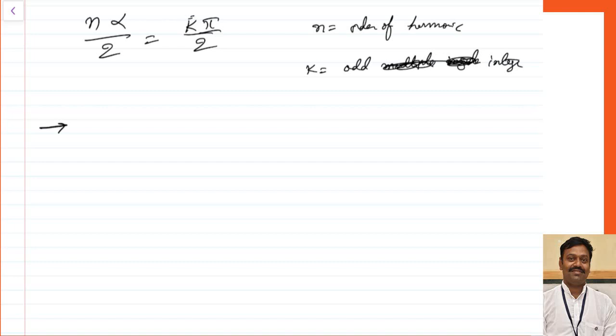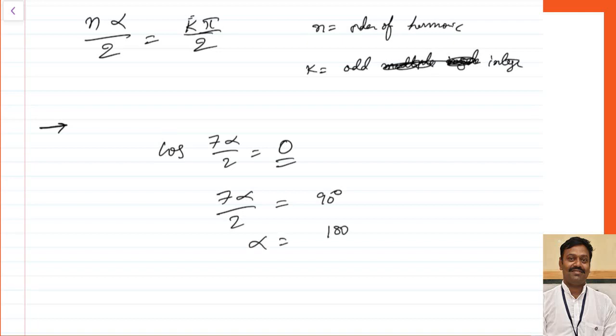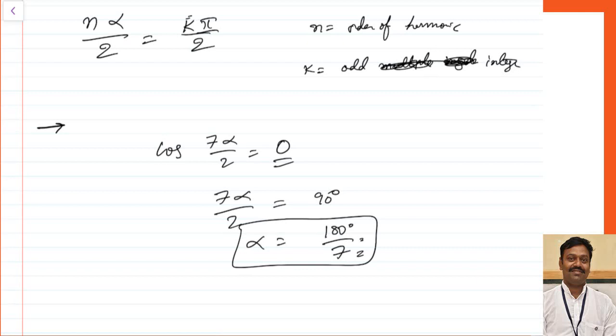Summarizing the short pitched coil: since the 7th harmonic is most dominating, we want cos(7·α/2) to equal 0, meaning 7·α/2 equals 90 degrees, or alpha equals 180 degrees divided by 7. By employing this cording angle, the 7th harmonic component is completely nullified. Always in an induction motor, the winding is short pitched by an angle equal to 180 degrees divided by 7.